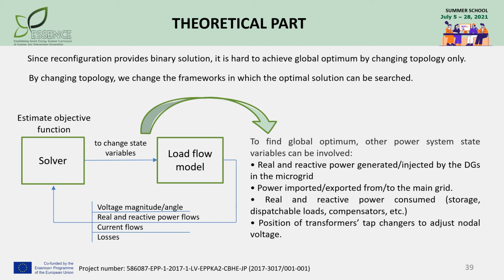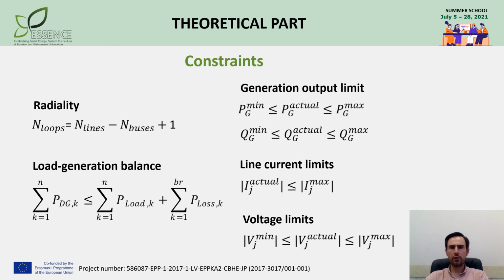The user defines which state variables can be adjusted to search optimum, like real power, reactive power of generators and loads, breaker states, transformer tap positions, and so on. And the solver varies them according to its internal logic. The outputs of the load flow model are used to estimate the objective function and find its maximum or minimum value among all considered cases. Since objective function shall be estimated for realistic cases only, the optimization task requires to consider system constraints.